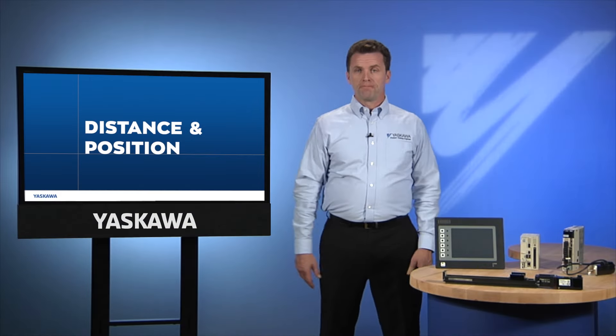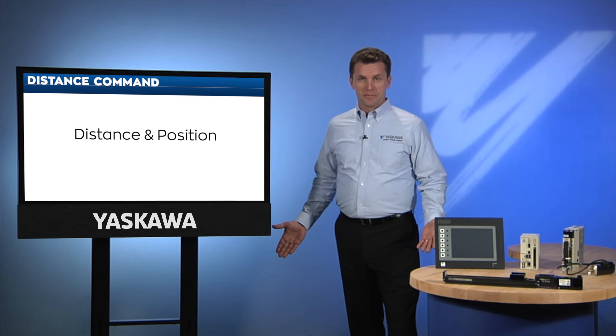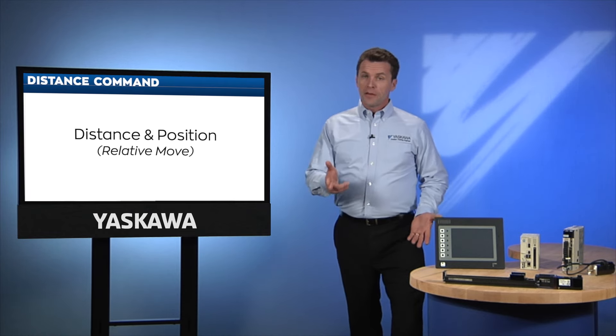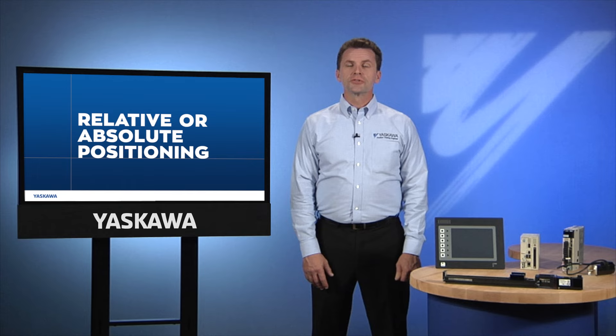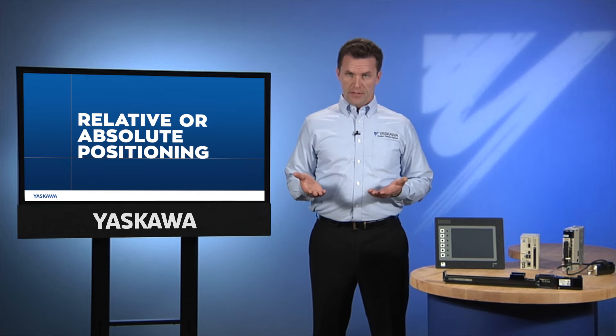Here's an example. If you order me to take three steps forward, that's a distance command — a relative move. If you tell me to go to the table, that's a position command — an absolute move. It's the same result, I'm at the table, but the type of command is different. Modern industrial motion controllers allow the programmer to define the move either relatively or absolutely, whichever makes the most sense for that particular part of the control program. For this reason, we really can't tell which method was used by simply looking at the machine in motion.